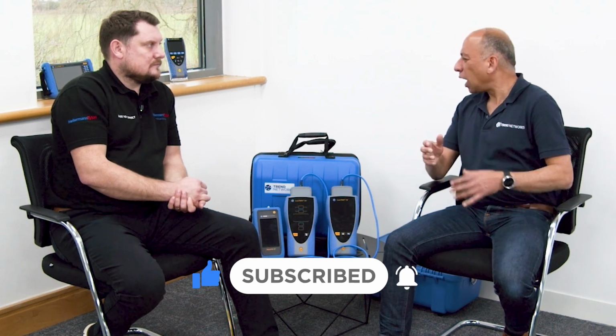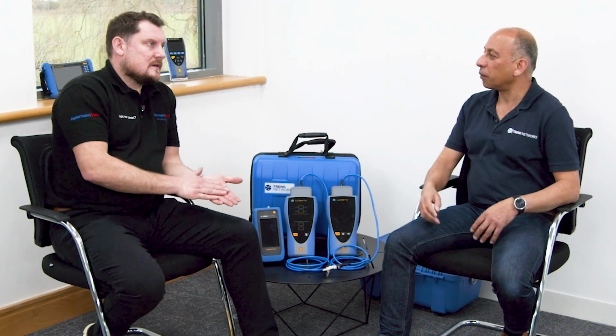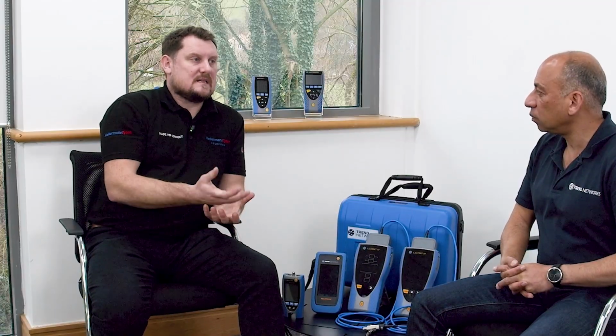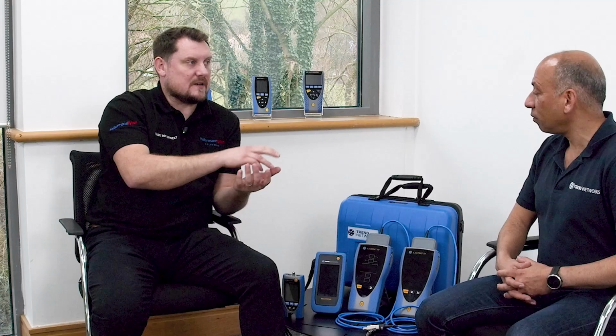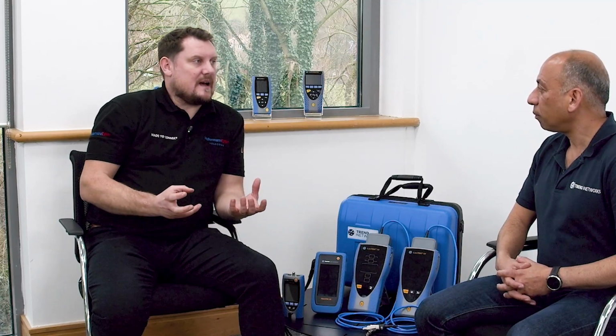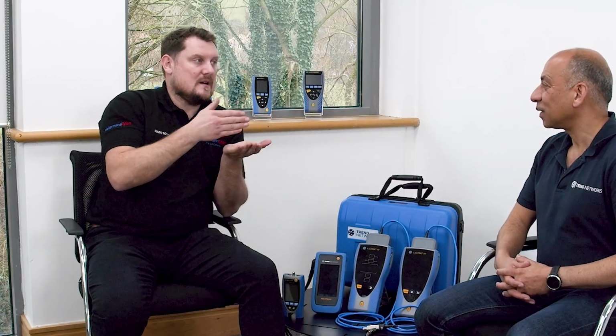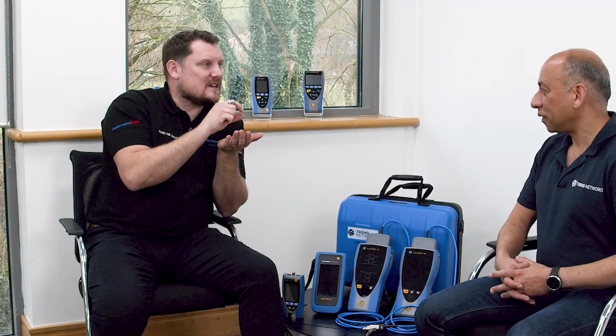Yeah, absolutely. Things like waterfalls - would you agree? How would we describe a pinch point to our listeners? It works both for copper and fiber. A lot of the time I see issues - within my experience, I've seen many issues related to copper cabling. With pinch points on copper cabling, it could be something as simple as the cables running over a basket tray. As we know, the basket tray has these periodical runs, and if you've got a large amount of, say, Cat6A cable bundles running over those, the cables at the bottom of that bundle are being squashed and squeezed against these runs. So these are really the pinch points.